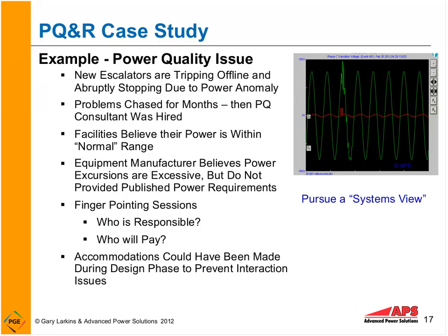But upon installation of these escalators, they found their new escalators are tripping offline. And you can imagine if you're on an escalator packing a bunch of luggage and all of a sudden it comes to a stop, that's not a good thing. So sometimes there were issues with personnel safety as well here.